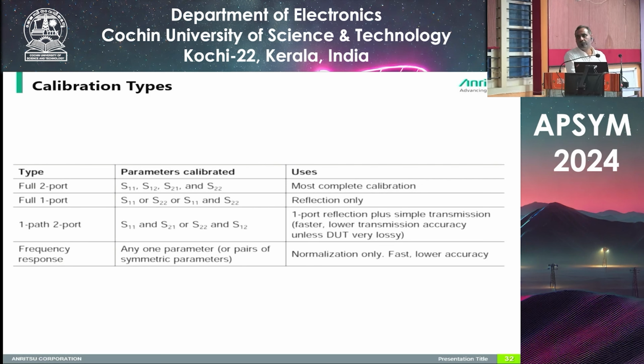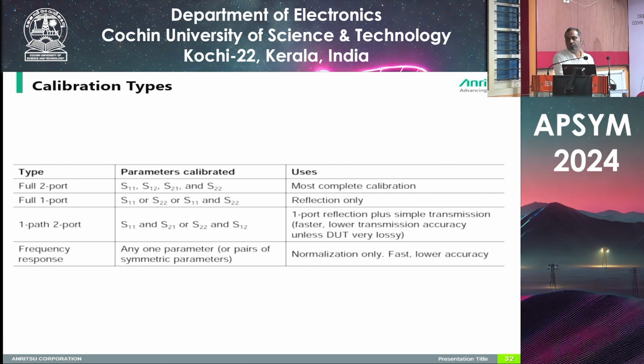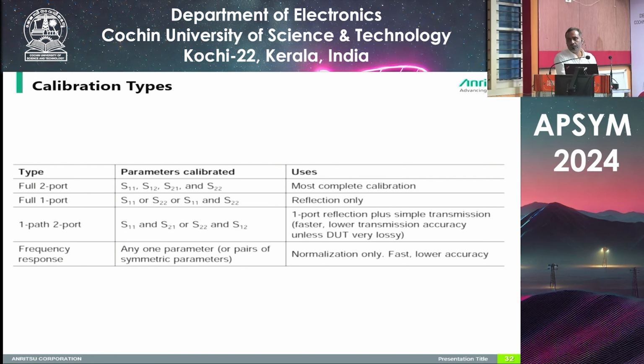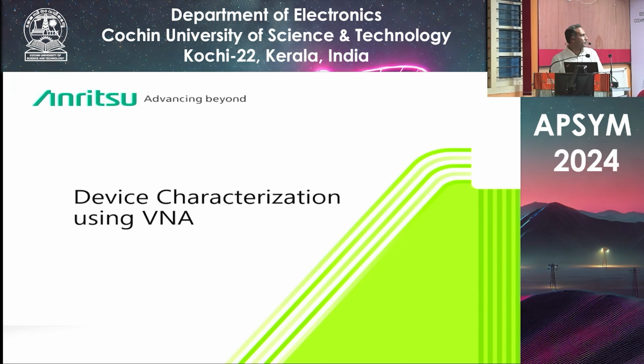Suppose you are doing only an antenna measurement and you want only the reflection parameter, you can select full one-port calibration, and you can do the calibration for only one port. Suppose you want to measure a filter or any two-port device, you can select full two-port calibration and do the calibration for both ports, where you can measure all four S parameters. Okay. So any doubts up to this? Anything?